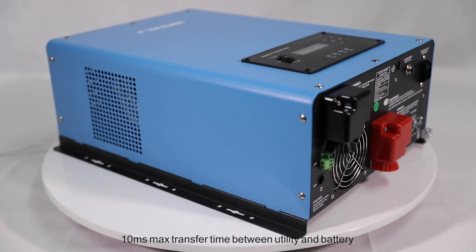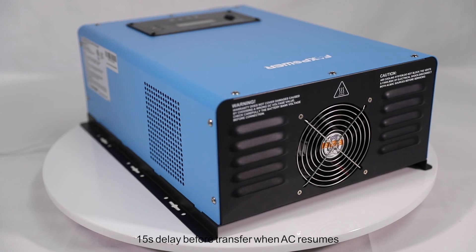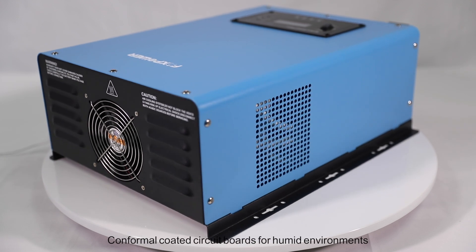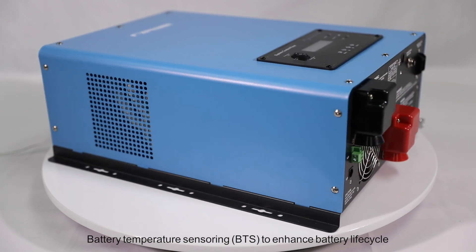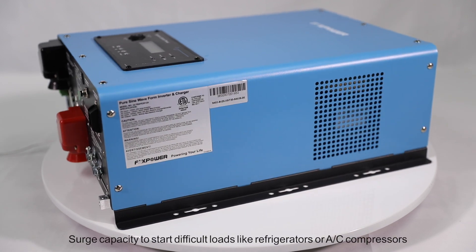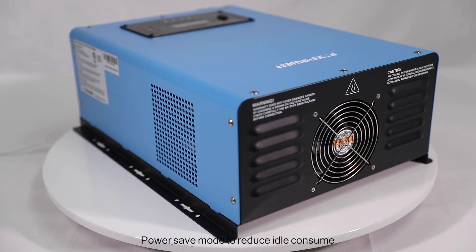Additional features include: power factor corrected multi-stage charger for fast, efficient charging minimizing charging time; 10 milliseconds maximum transfer time between utility and battery, guaranteeing power continuity; 15-second delay before transfer when AC resumes, providing protection for loads when used with a generator; conformal coated circuit board for humid environments; battery temperature sensing (BTS) to enhance battery life cycle; LCD and LED display to indicate the status of the inverter charger; and surge capacity to start difficult loads like refrigerators or AC compressors.